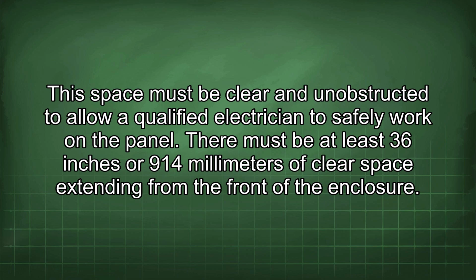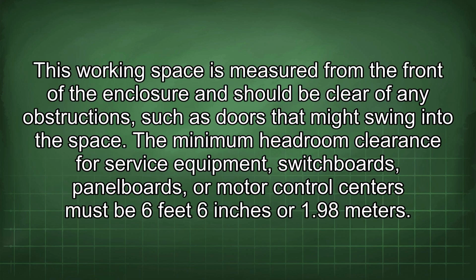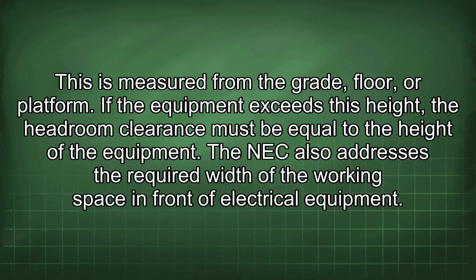There must be at least 36 inches or 914 millimeters of clear space extending from the front of the enclosure. This working space is measured from the front of the enclosure and should be clear of any obstructions, such as doors that might swing into the space. The minimum headroom clearance for service equipment, switchboards, panel boards, or motor control centers must be 6 feet 6 inches or 1.98 meters. This is measured from the grade, floor, or platform. If the equipment exceeds this height, the headroom clearance must be equal to the height of the equipment.